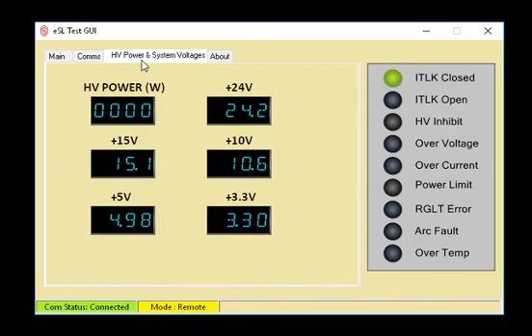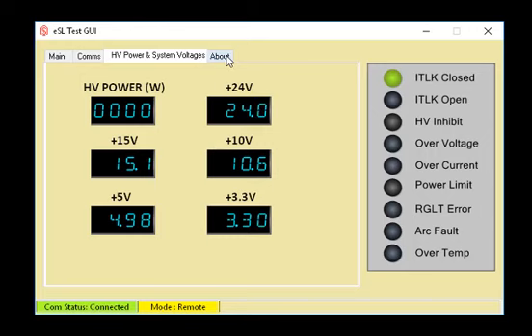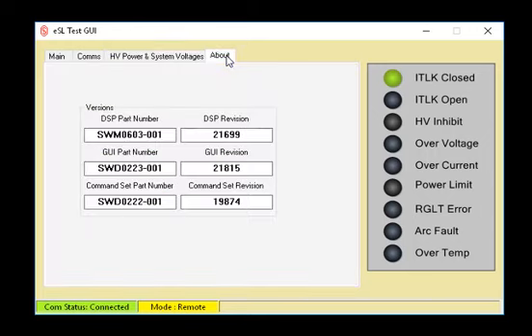Let's click the high voltage power and systems tab. This box will display the output power in watts when high voltage is enabled. These other boxes display the internal housekeeping voltages of the power supply.